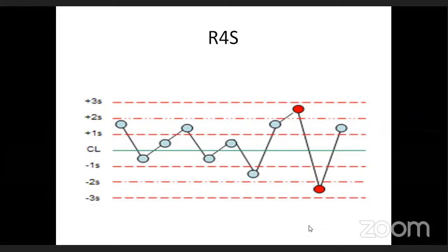You must look at several other features. That means you have multi-sample controls which you should look into. If you have only one particular reagent giving you a bad result, that means the system is working fine except for that particular test. Or if you have several failed QC for different tests for different reagents, it indicates that there is a mechanical problem in the probe, the reaction cells, in the lamp, and you must do your troubleshooting according to that.